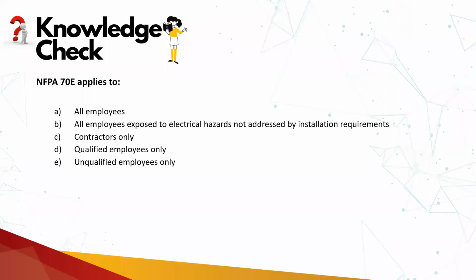So now 70E is going to apply for all qualified and unqualified employees who will be around that particular working area. So the requirements for limited approach boundary, restricted approach boundary, and arc flash boundary, creating awareness, and whether you have to perform the job after establishing an electrically safe work condition or perform the job live, and so on, all those things will be applicable as a part of the NFPA 70E requirements or standards.